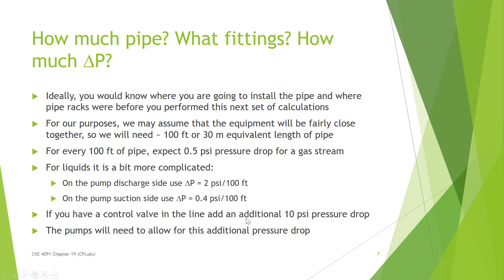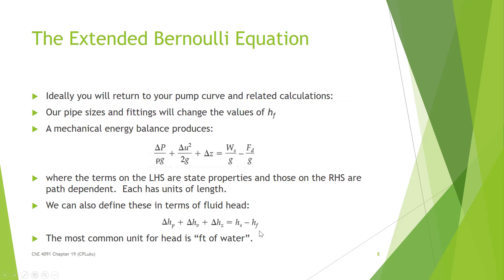Sometimes we apply a blanket 20% excess design factor just to make sure we have adequate flow, particularly when we don't know what the maximum flow will ever be. You want to make sure you accommodate this. We then go back to where we were when talking about pumps — back to the pump curve and all those calculations. These pipe sizes and fittings are going to change the values for head losses (h sub f, the frictional losses), and we need to redo the extended Bernoulli equation calculations and verify where we are on that pump curve.